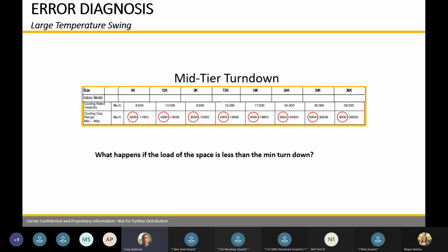So we have to look at turn down of these units too. If we have a 12,000 BTU, it can only turn down so low if they only have it in a little room and they threw a 12,000 in there. So large temperature swings could be because the unit is oversized. It's giving you a rush of heating, and by the time it turns off, the room is overheated. So need to look at that as well, the size of the unit for the size of the room.